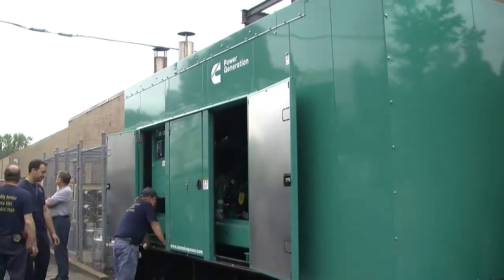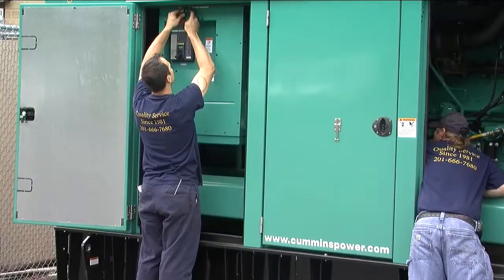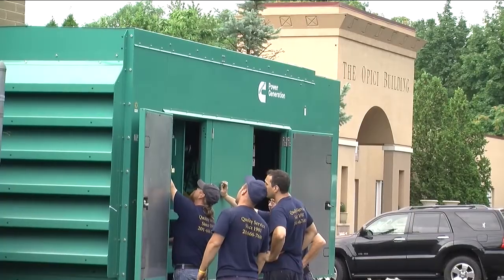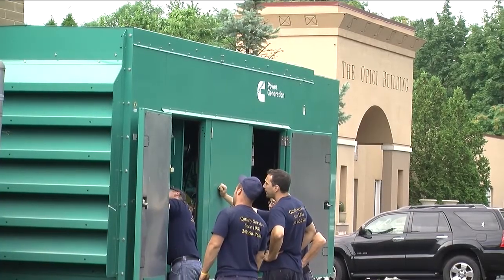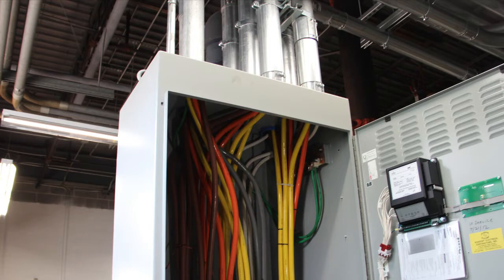You can see that we have set this generator onto the concrete pad outside Opici Wine. Now we're going to start with the installation of the electrical conduits to bring the 480 volt three-phase power from the 500 kilowatt Cummins diesel generator into the automatic transfer switch inside the building.